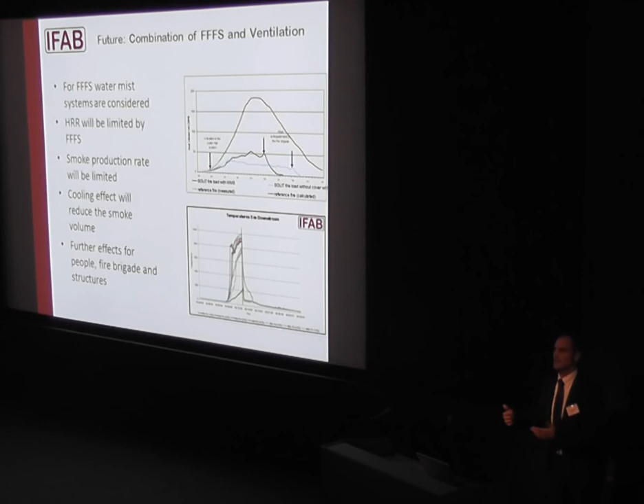So it's considered that you can use a combination of water mist and the ventilation system. Why? On the one hand, the heat release rate will be limited. The truck fire I showed you, if you just would let it burn without any fire suppression system, you can get easily 150 megawatt. So it was limited to 50 megawatt. That's a good thing. Of course, the smoke production rate is reduced. Even more important is the cooling effect of the water mist. Because of the cooling effect, you reduce the smoke volume dramatically. And when you reduce the smoke volume, your existing smoke extraction or ventilation system is much more effective.